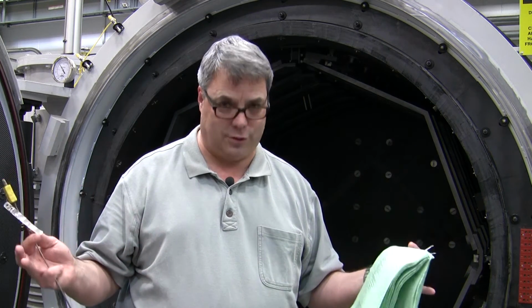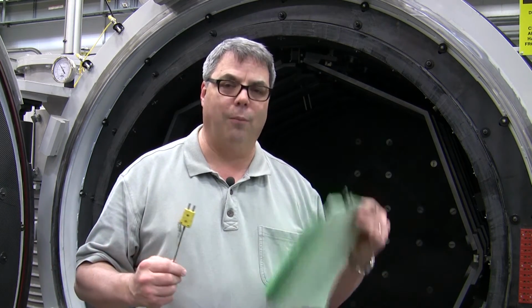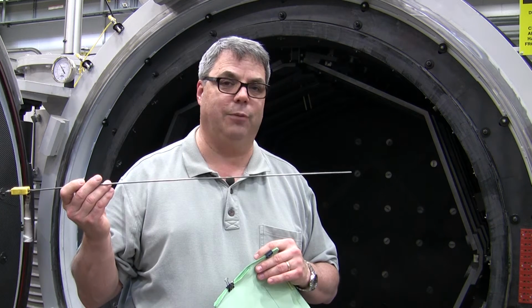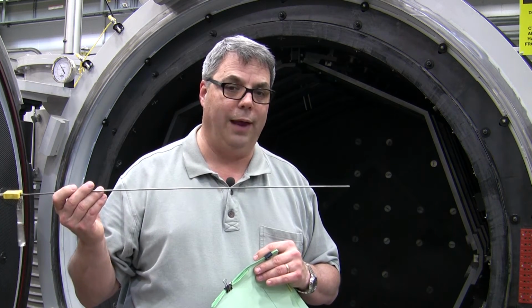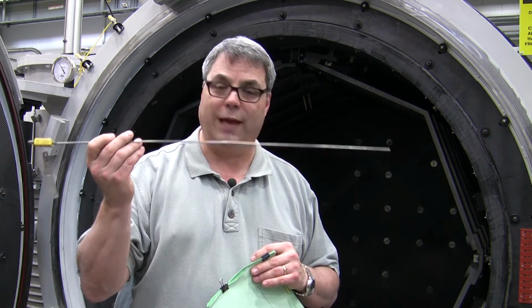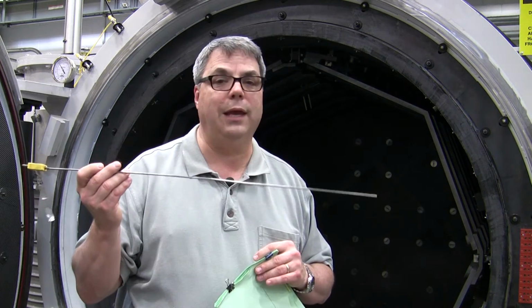You will hear both sides argued. You will hear customers on both sides. You will hear inspectors on both sides. But I'm finding it more and more common in the industry. If you're recording the TC immersion depths and can prove it, and it's from a like family calibration curve, there's no need to recertify the machine and invest an additional 24 hours of your time.